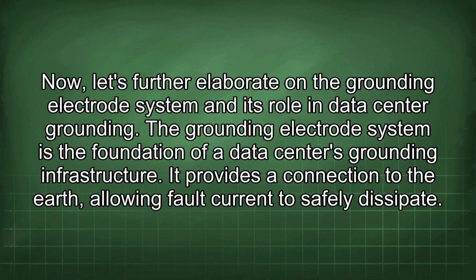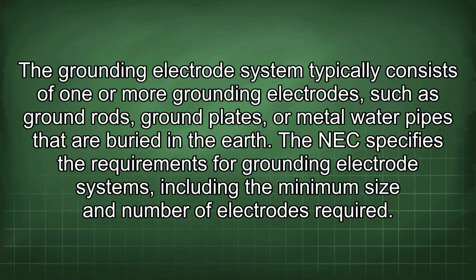Now, let's further elaborate on the grounding electrode system and its role in data center grounding. The grounding electrode system is the foundation of a data center's grounding infrastructure. It provides a connection to the earth, allowing fault current to safely dissipate. The grounding electrode system typically consists of one or more grounding electrodes, such as ground rods, ground plates, or metal water pipes that are buried in the earth.